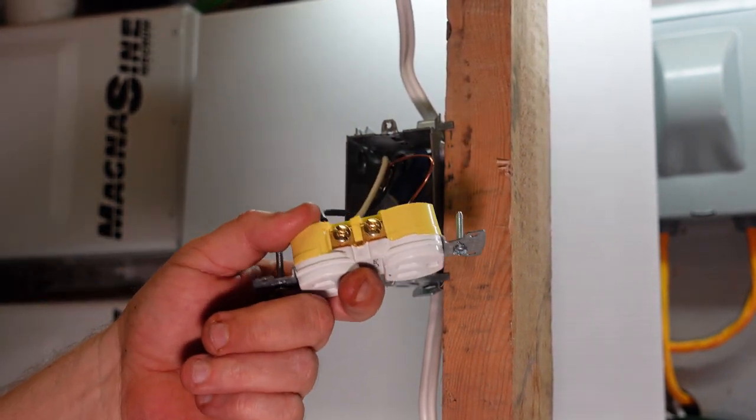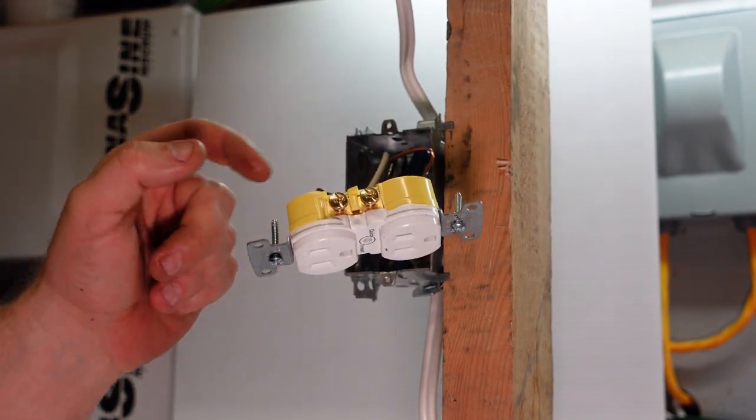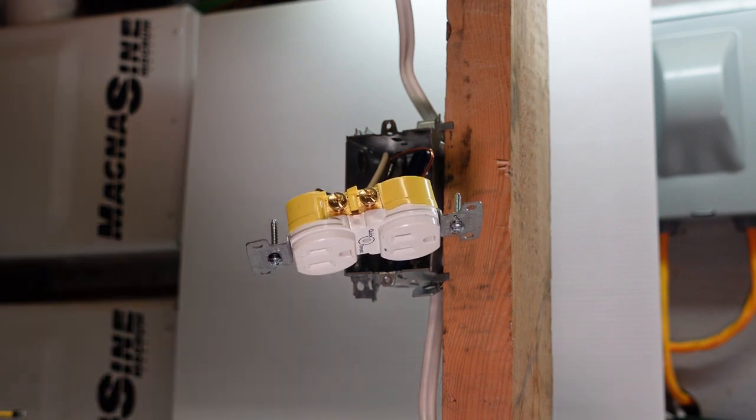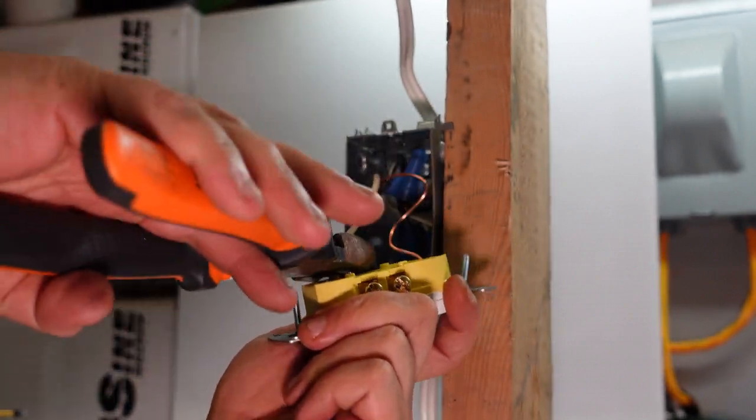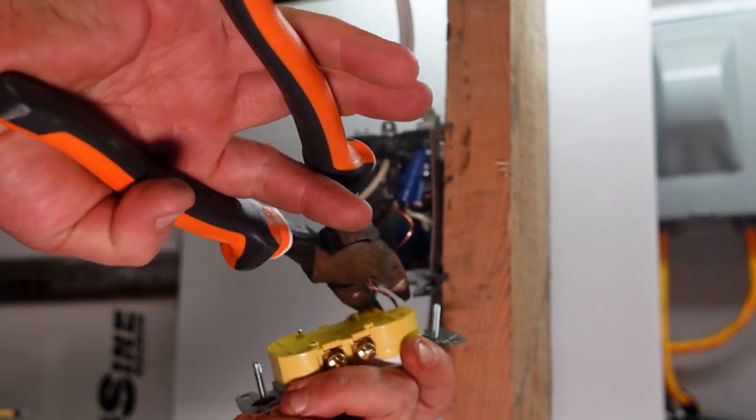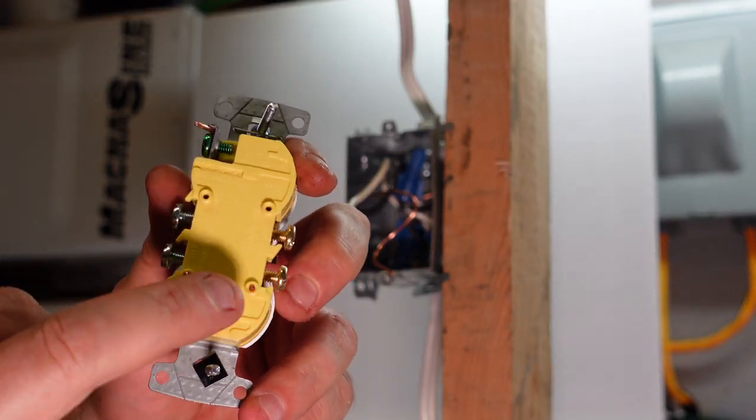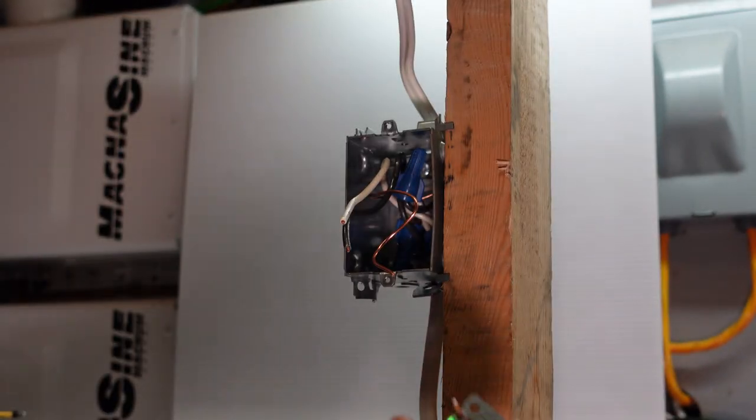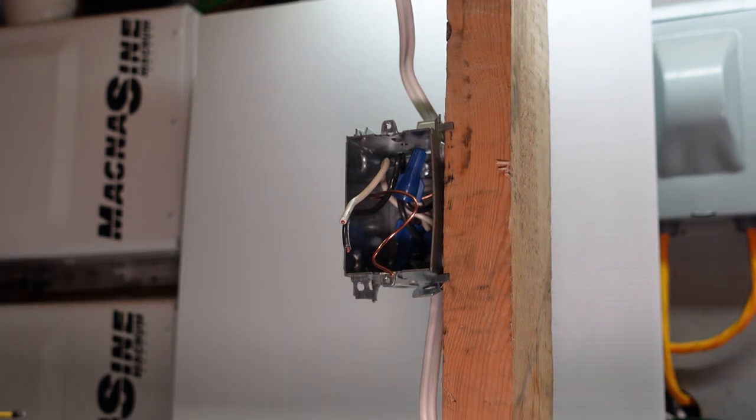So this plug issue, unfortunately we don't want to just go ahead and cut them off the back, which is what we have to do to repair it. We don't recommend that we would ever use the same receptacle because then what happens is on the back of the receptacle you actually have the little copper tab sticking at the back, which is also not a good situation to be in. So we're gonna get a different receptacle.